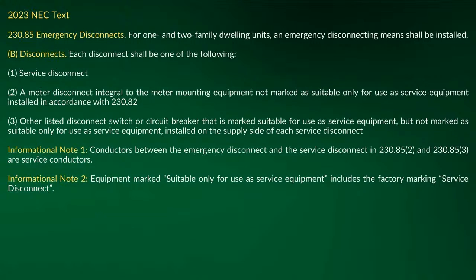All right? Right. Now, this is what I'm going to tell you here. If I have my emergency disconnect there at that dwelling, what you have to establish at this point is, does the disconnect have overcurrent protection that's been established at that disconnect or not? Now, if I just have a disconnect, all it is, it's nothing more than a disconnect, and it's on the supply side, period. Right. And then I can take that neutral, and that neutral can be used to bond everything in, okay? Right. But if I establish overcurrent protection there, I will contend that is your first point of disconnection for that building.